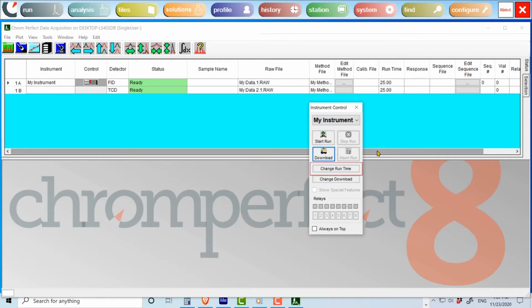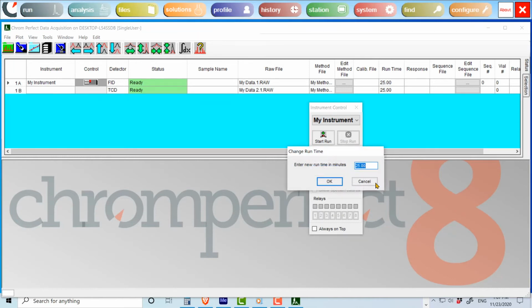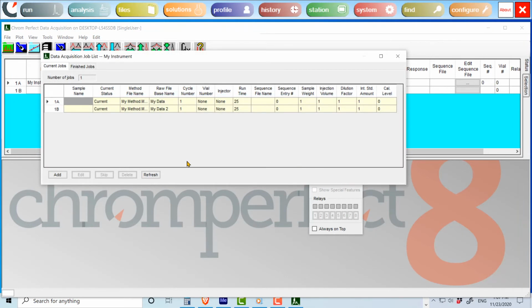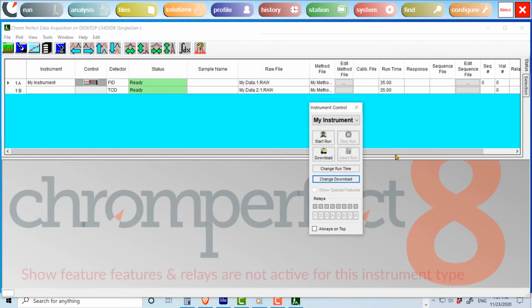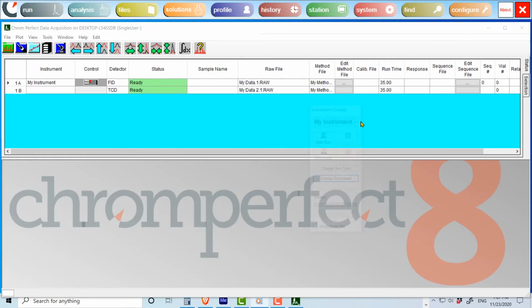Change runtime. You can change the runtime to increase the run if needed. This can be done even when data is being acquired. Change download. Edit a sequence that is currently running to add or delete a sample. Show special features. Check this box to access the instrument panel. You can also upload setpoint files, instrument parameters, from a Direct Connect digital instrument. Relays. Shows the state of the relays on Tiger interfaces, and you can change these manually here.